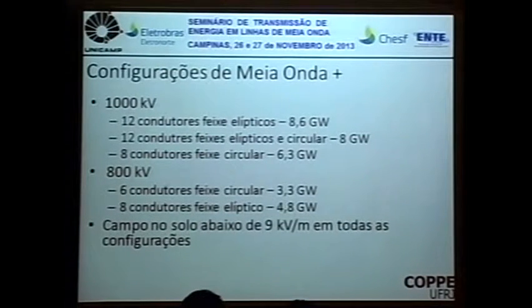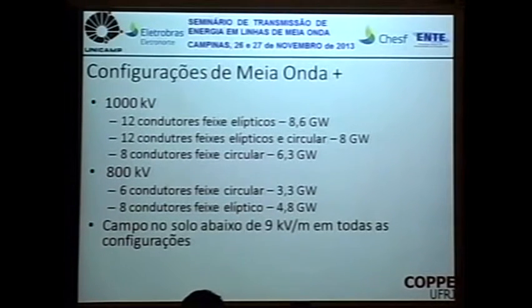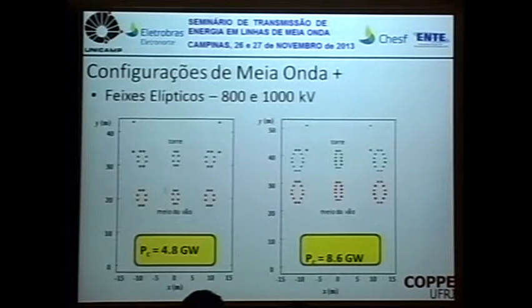And the project of this line was done in detail, always thinking about the physical conditions. We always established the behavior using Maxwell equations, and from the Maxwell equations, we derived the circuit elements. For all configurations, our field on the soil never exceeded 9 kV per meter, within what we consider proper for the Brazilian standards. Just to demonstrate the 800 kV beam, basically 4.8 gigawatts.